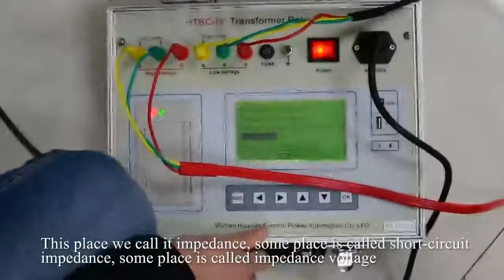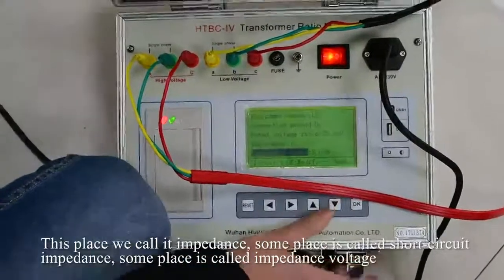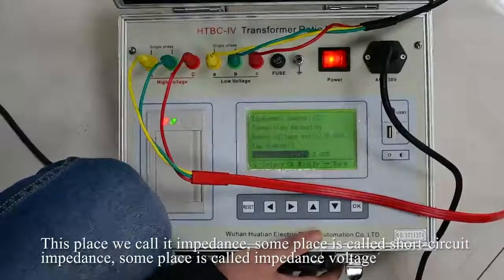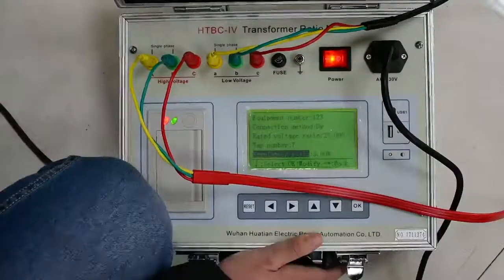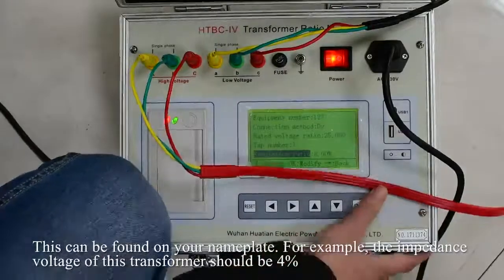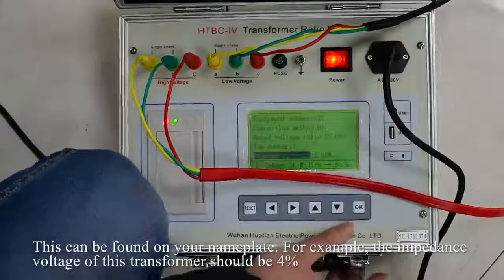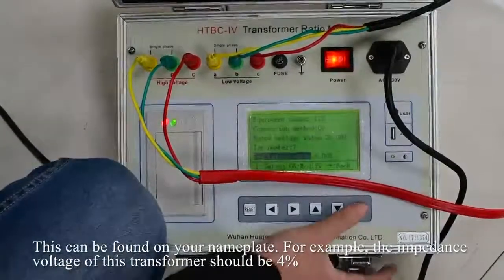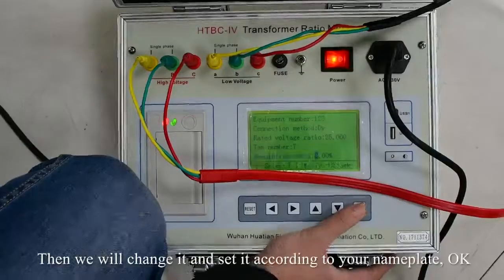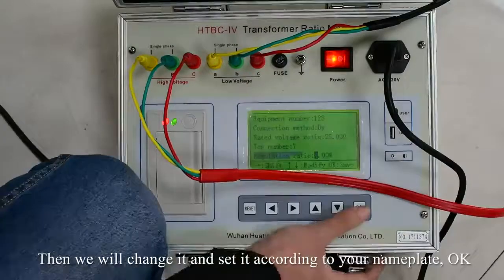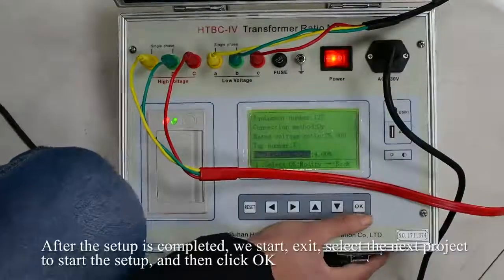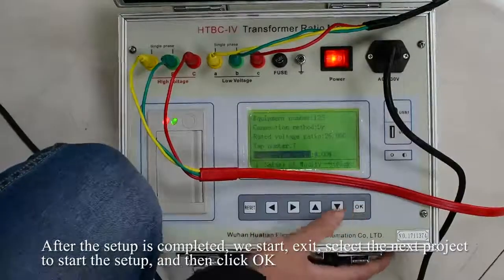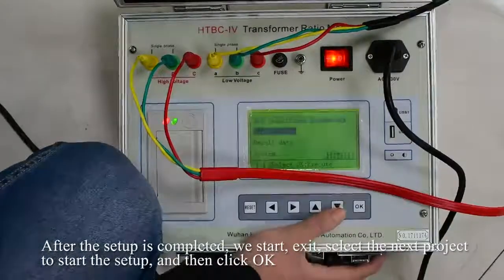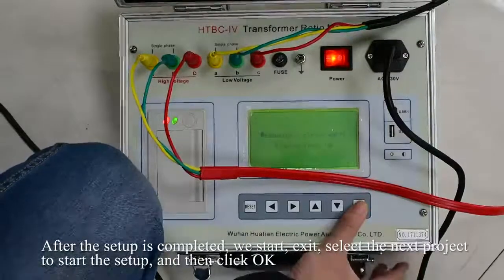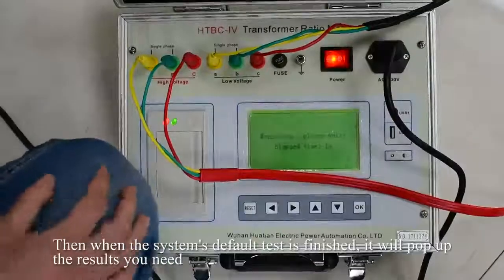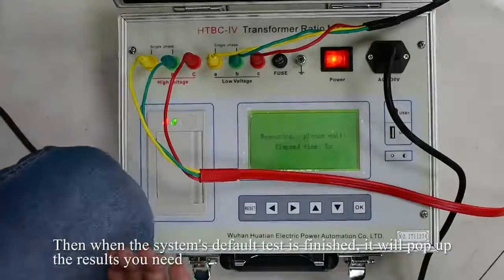This place we call it impedance. Some places call it short circuit impedance. Some places call it impedance voltage. This can be found on your nameplate. For example, the impedance voltage for this transformer should be 4%. Then we will change it and set it according to your nameplate. OK. After the setup is completed, we start, exit, select the next project to start the setup, and then click OK. Then, when the system's default test is finished, it will pop up the results you need.